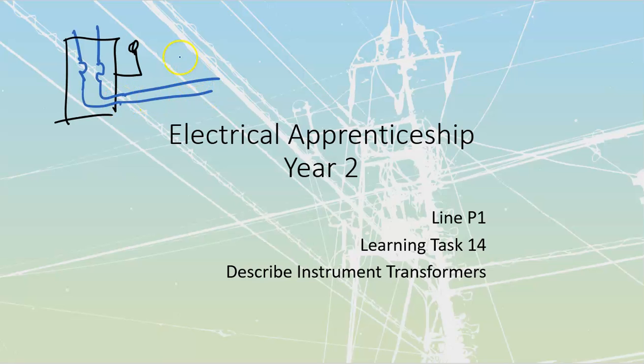It would be really difficult for BC Hydro to put in an inline meter, the same as those meter bases on the side of a house, that gray socket with the round hole you plug the meter into. Those meters are rated to no more than 200 amps. If they had to directly carry 400 or 600 amps, the meters would need to be incredibly large, bulky, expensive, and non-standardized.